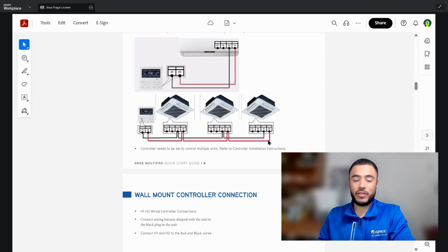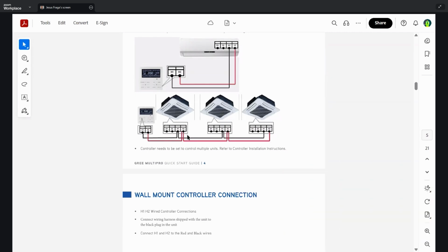Depending on how many indoor units you have and you want this wired controller to control is how long your daisy chain will be. Please remember that the wired controllers are only capable of doing up to 16 indoor units via one controller. So just keep that in mind.